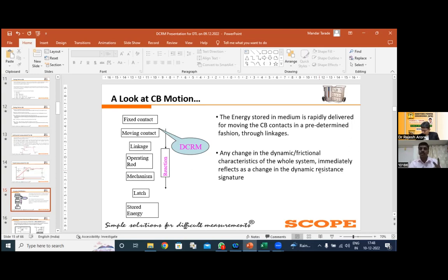So two things are very, very important at the time of performing the travel operation. The first one is the electrical stroke length, which is available on all the transducers used to perform the travel operation for the CB, because according to the mechanism there are several types of transducers available. From manufacturer to manufacturer the mechanisms change, and accordingly the transducers also change.